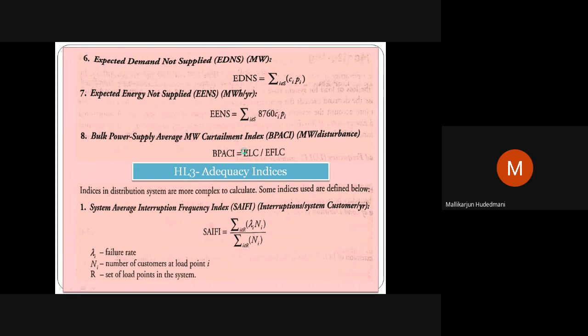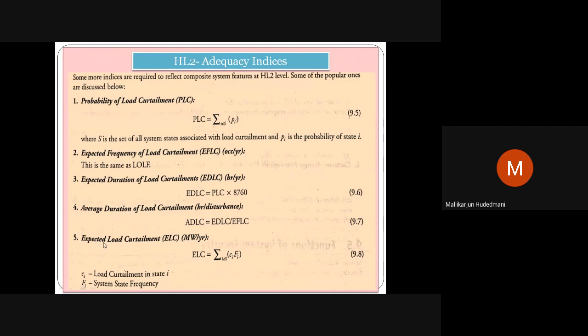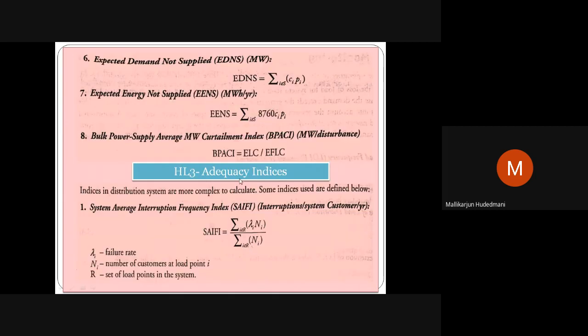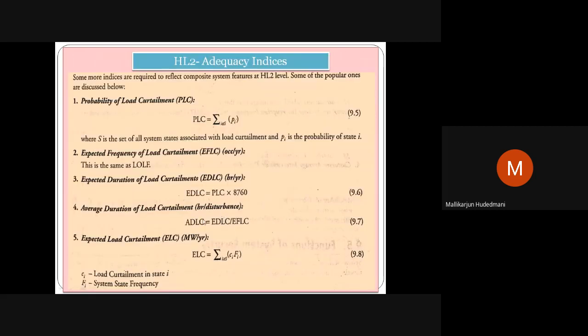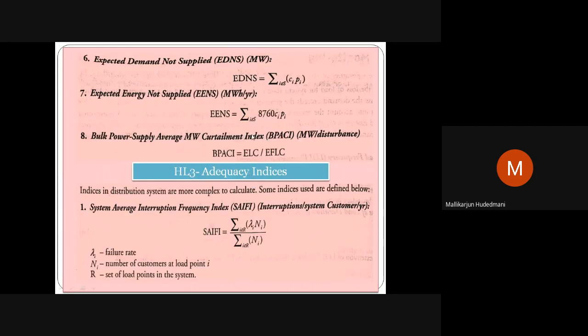BPACI is ELC divided by EFLC. What is ELC? Expected load curtailment, which is not being met in a year, in megawatt per year — total quantity of megawatt in terms of power not being addressed in a year. What is EFLC? Expected frequency of curtailment, in terms of number of times not being served. So total energy not served divided by total times not served — that ratio becomes the bulk power supply average megawatt curtailment index, which is megawatt per disturbance: per disturbance, what is the loss, the average. All these are average values because we are taking the number of disturbances in the denominator.